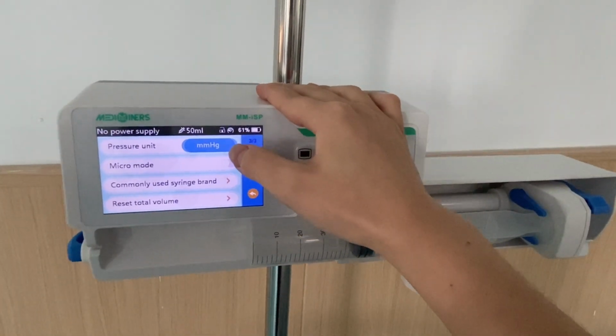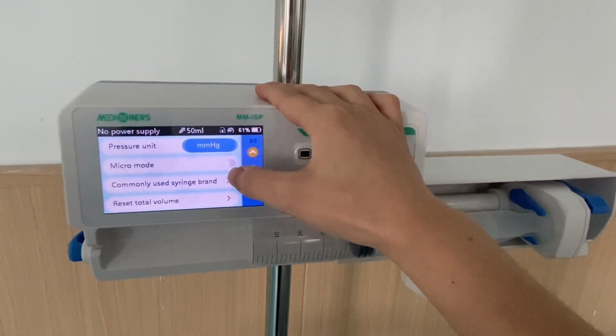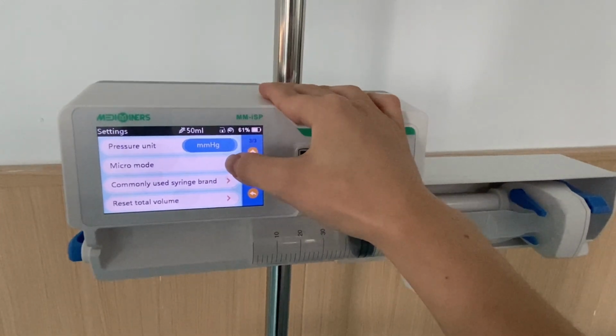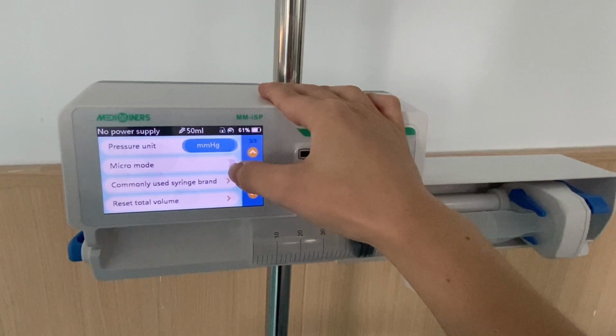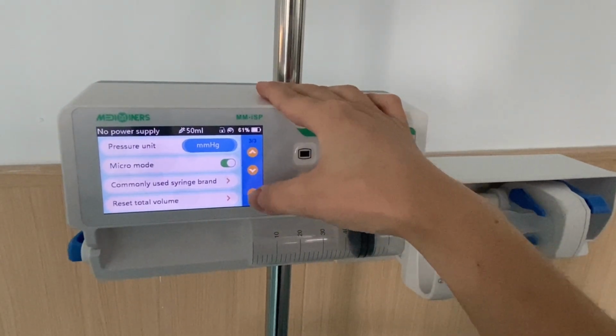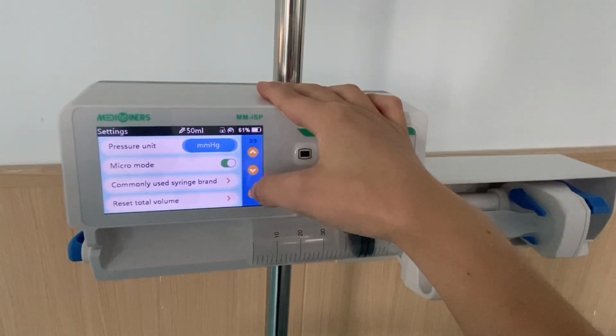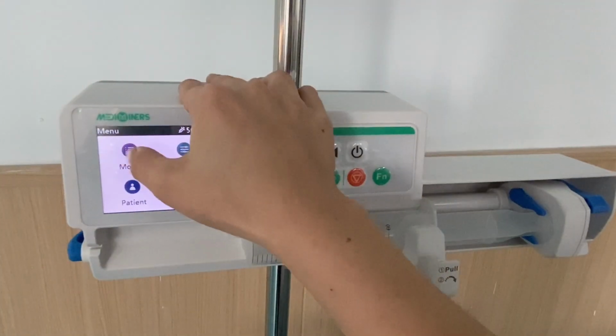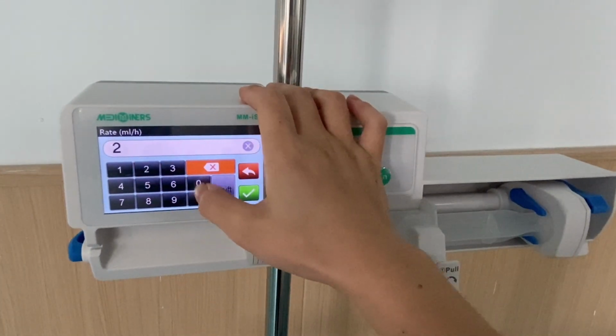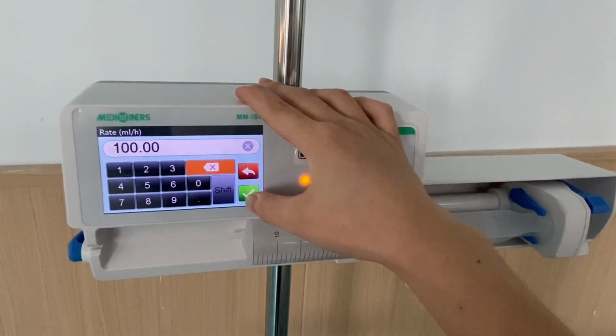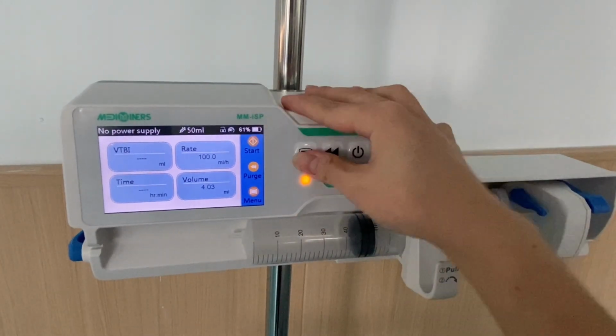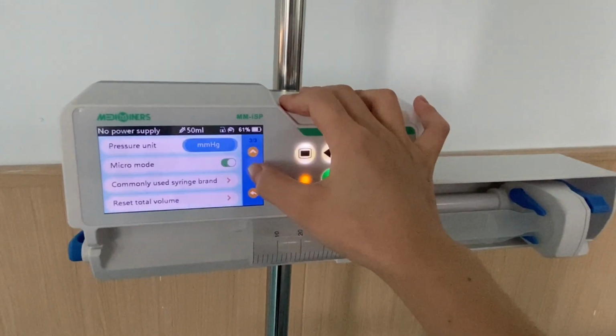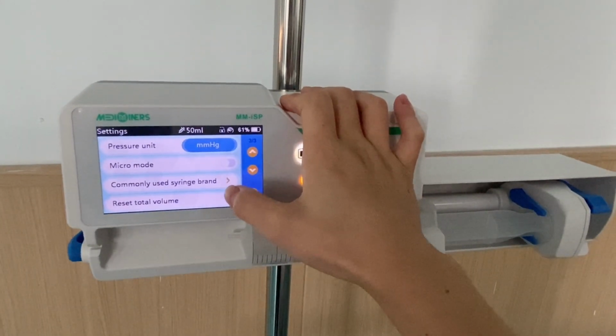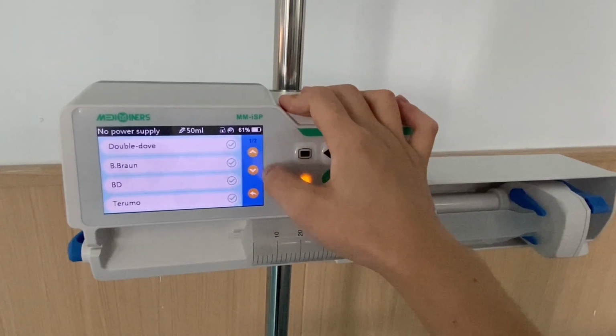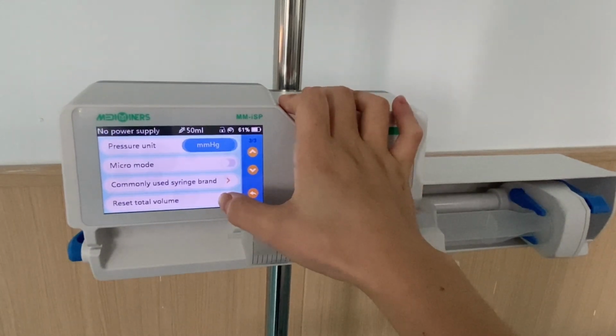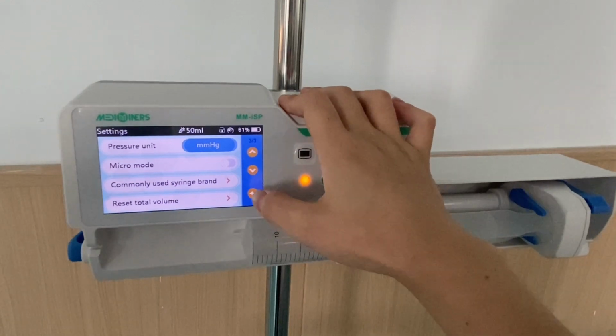This is the micro mode. Micro mode is for meeting the requirements of an ICU and some newborns. We should limit the maximum flow rate for them to protect them. If we activate this, then the maximum flow rate for all syringe sizes will be less than 100 milliliters per hour. We can go back to see the settings. If we want to select 2000, no, it will only be 100. Then the commonly used syringe brands. We already have 5 syringe brands here. And the reset total volume means data clearance.